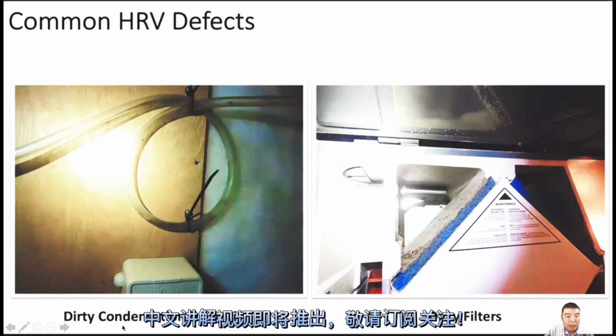Okay, dirty condensate drain line. This HRV, in fact, is not like a humidifier. A humidifier has lots of water, maybe a lot of water draining out. But an HRV only in winter time, only during defrost, will have water come out. But still the pipe is sometimes very dirty. Even though there's a filter inside, some dust still goes through, mixes with water and comes out from the drain line. So if this drain line is too dirty or clogged, it needs cleaning.